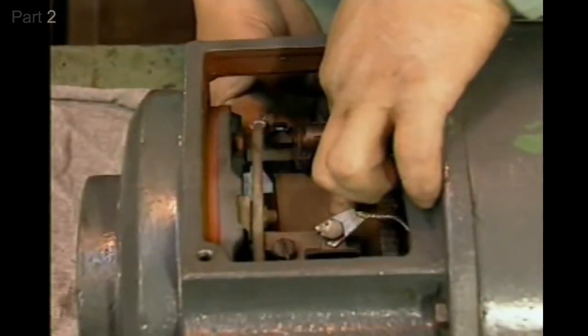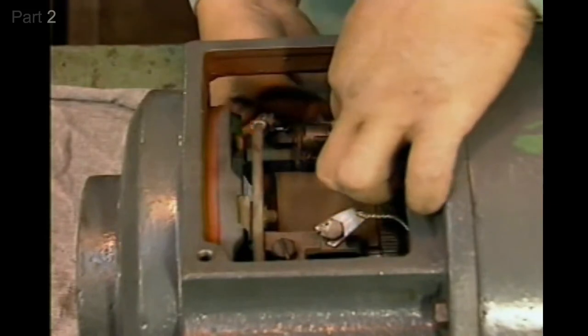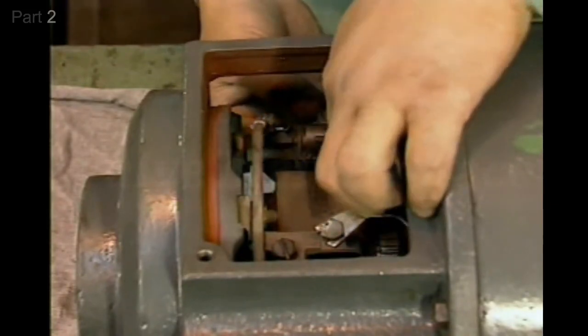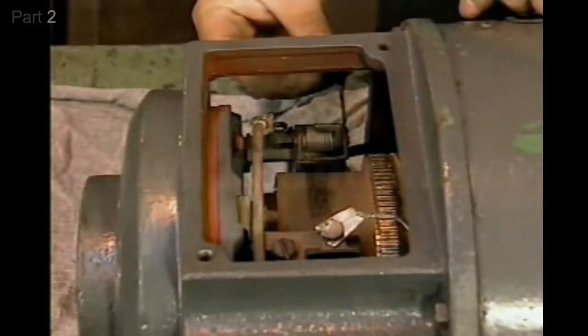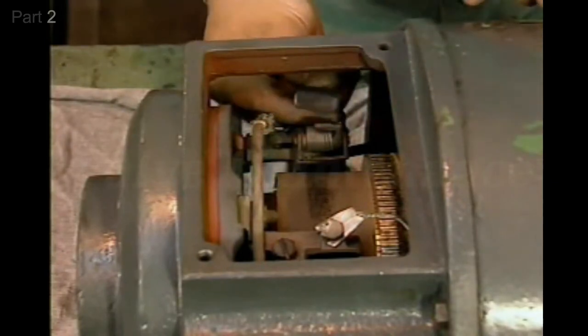In this example, the motor's armature is then turned slowly back and forth a few times. The brush is then removed and inspected to see if it has the same shape as the surface of the commutator.